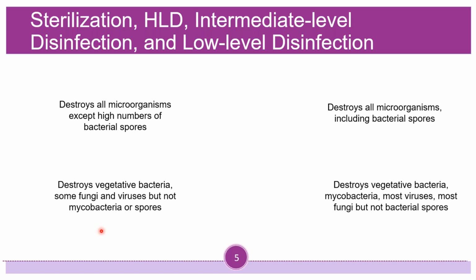Now, in this specific example, in this slide, you can see all of the different classifications, right? And you know that sterilization, high-level disinfection, intermediate level, and low level are going to match with one of them. When you're taking the test, you're not going to have that. So you need to make sure that you're able to pick out which one it is. Okay, so I'm getting a ton of high-level disinfection, which is correct. Good job, 5 stars. All right, next one. Destroys all microorganisms, including bacterial spores. We're on this one.